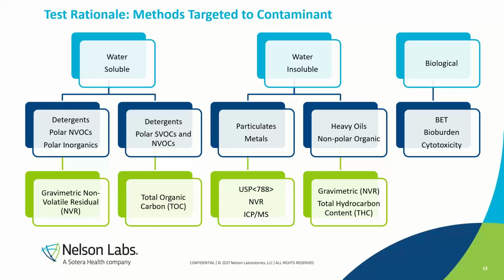If your device has polymer components, it's not going to work well with that hexane. If you're working with another THC method that does offer alternative non-polar solvent extraction options, like maybe it extracts in IPA and then goes on the analyzer, that might work for you. But our method at this time is just hexane only, so it's not going to be compatible with polymer components, in which case we need to switch it over to the gravimetric method to detect those oils.